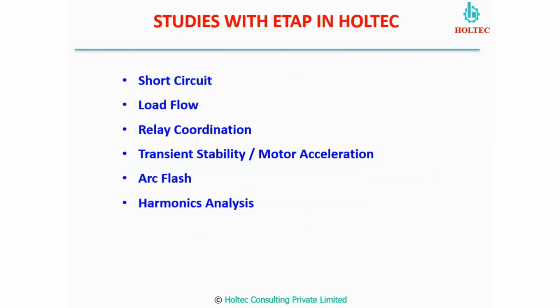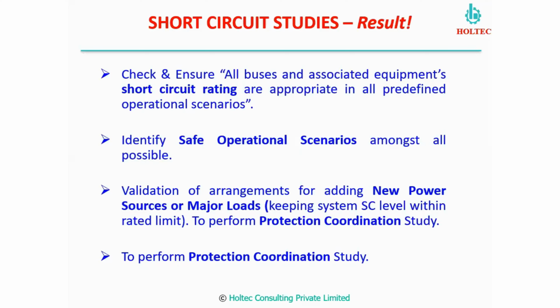What are the results which we can obtain from these short circuit studies? The first thing is that all buses and the associated equipment ratings we can validate or decide, so that your system will be safe. The next one is the safe operational scenario amongst all possible options. As I have already told you, there are multiple operational scenarios available in any power distribution system, so we can check which is the safest one to operate. Then we can also validate the addition of new power sources and major loads. And last but not least, it is a very useful requirement to conduct a protection coordination study.